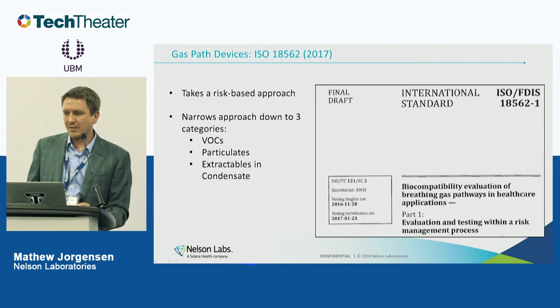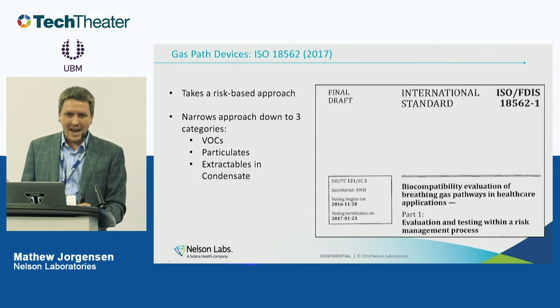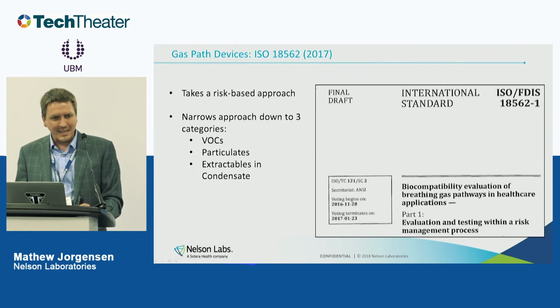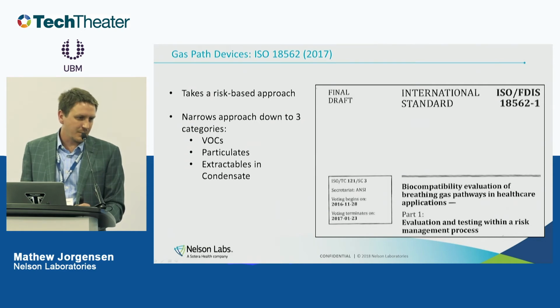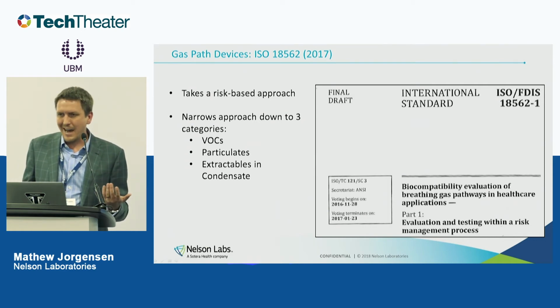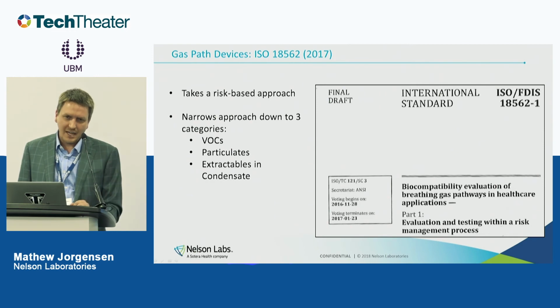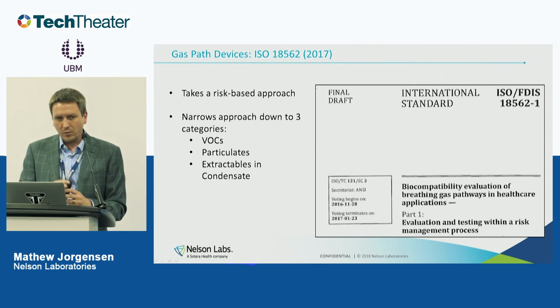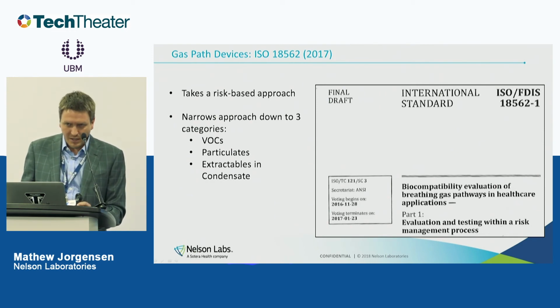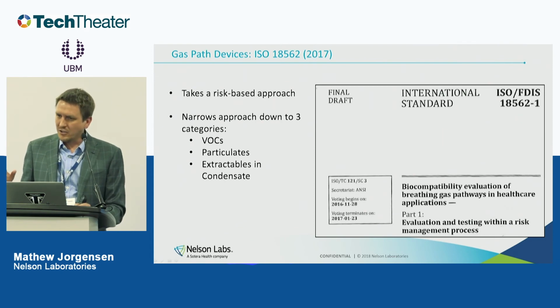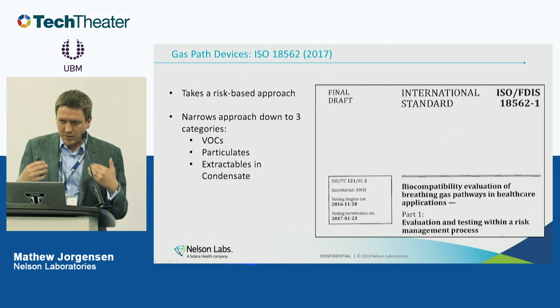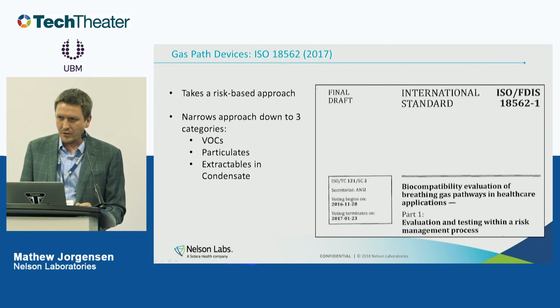If you have a gas path device, the risk that it has is really whatever it can carry in the gas to the patient. Gas passes through the device, it touches the patient's lungs. What can be inside the gas? Volatiles and particulates. So if your device is one where that's its only contact, then you just need to measure the volatile organic compounds that can be carried from the device and check if it can release any particulates, and have those evaluated for safety, and then you're done.